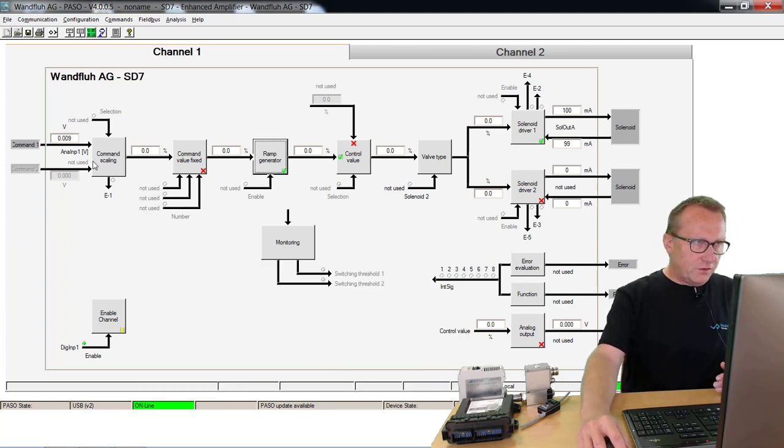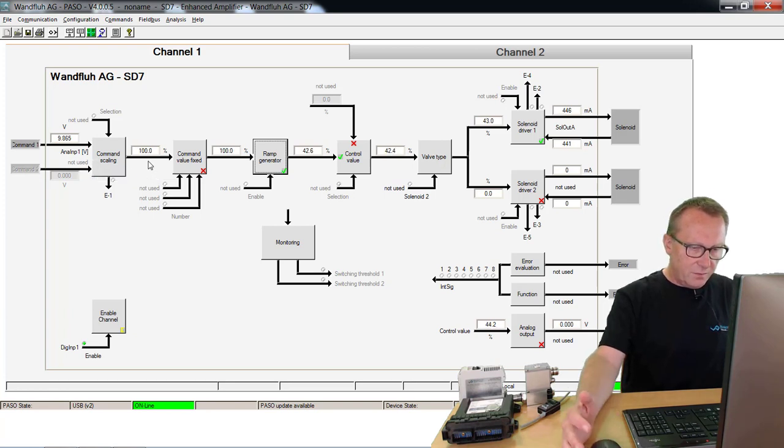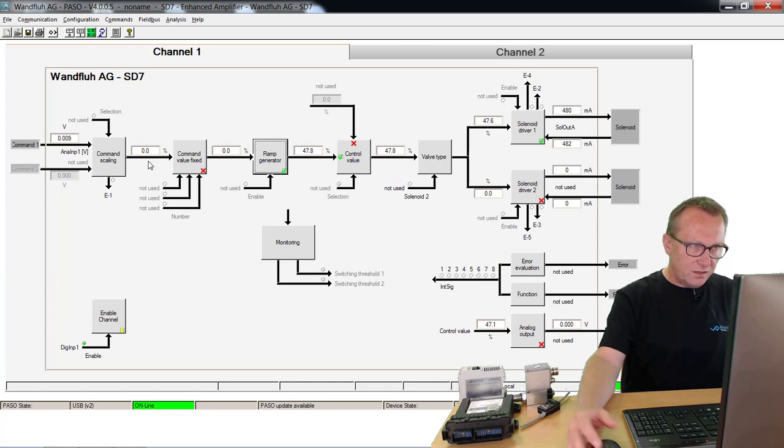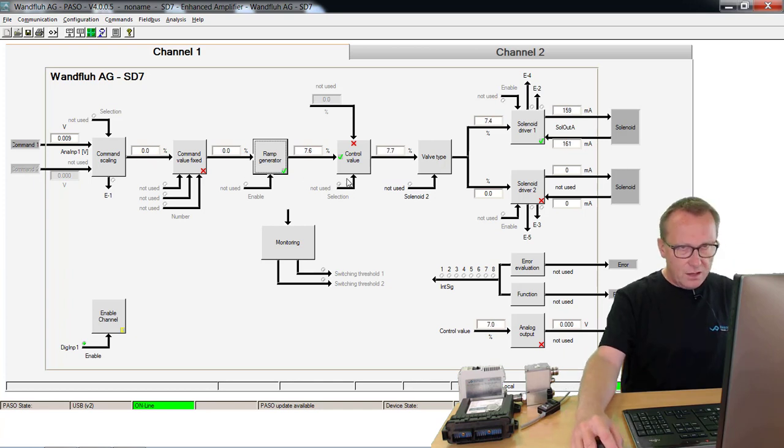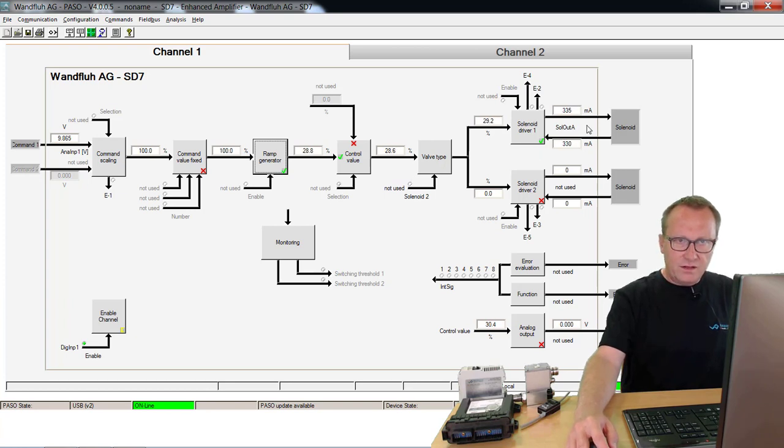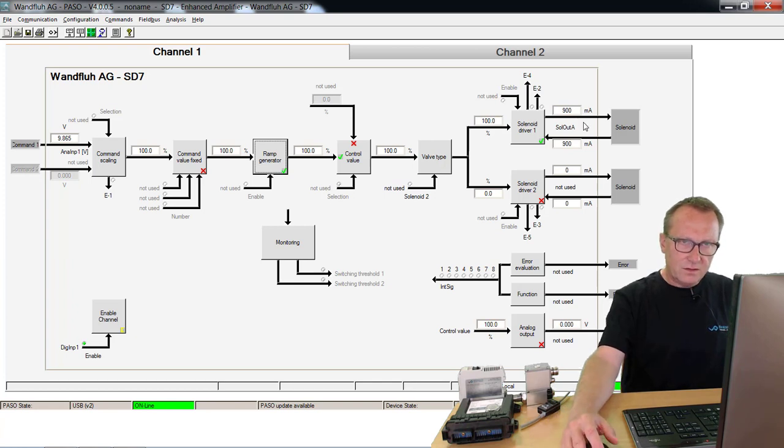If I switch on now my system, the input signal still changes immediately to 100% or changes immediately to zero percent because here I have no delay. But on the output side, if I switch on, it takes now two seconds until the current will be 900 mA.